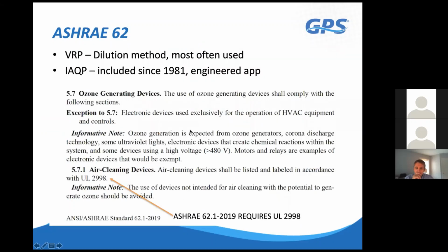Now, as I mentioned earlier, we use ASHRAE Standard 62, the indoor air quality procedure, to clean up the air in your building by using this technology such that you can recirculate it. It takes care of the contaminants of concern, and you can reduce your outside air requirements. And we do have software, which we're not going to get into today for the sake of time, that will calculate both methods, the VRP and the IAQP. And what's nice about the software is that you don't need to have any more data to run the indoor air quality calculations than you already need to know in order to design with the ventilation rate procedure.